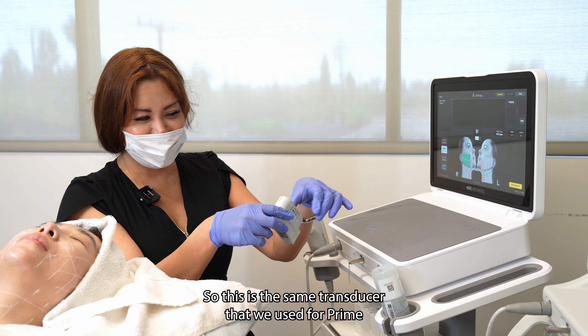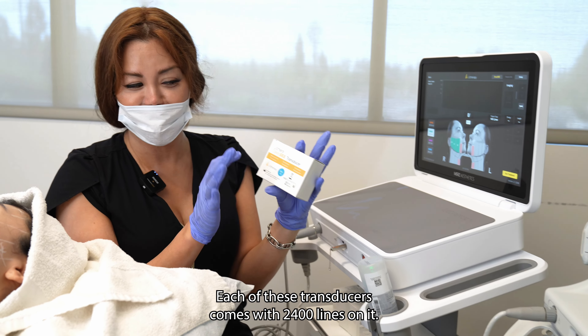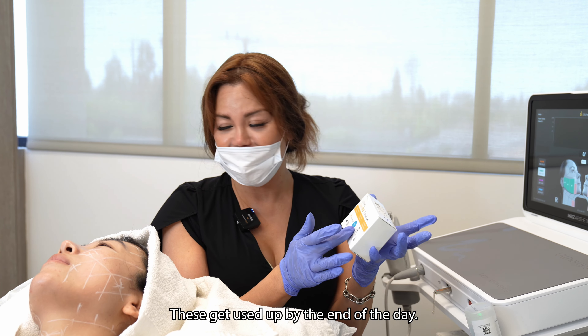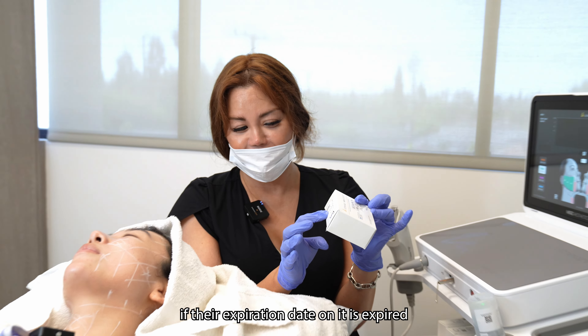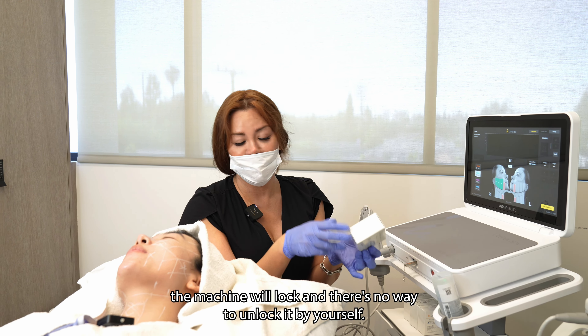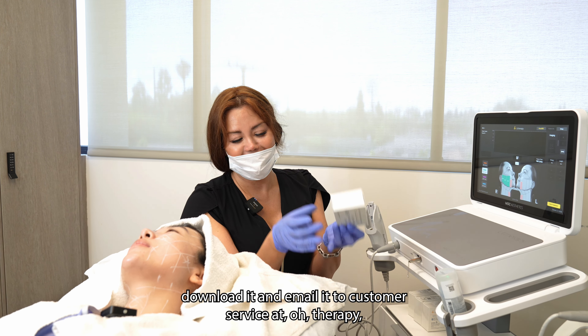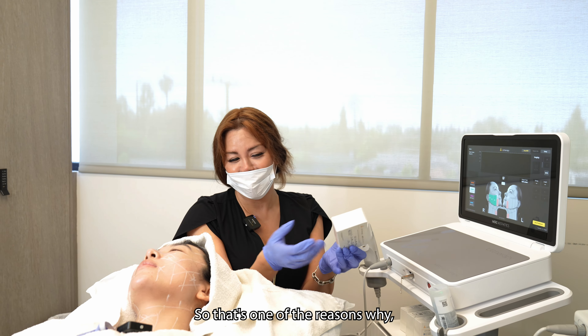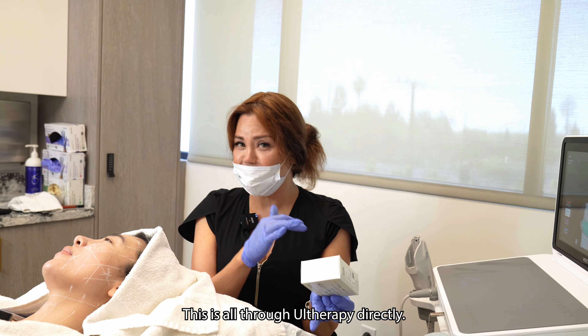This is the same transducer that we use for Prime that we're going to use for Ultherapy the original. Each of these transducers comes with 2,400 lines on it, and we, especially at WAVE, go through these extremely fast. These get used up by the end of the day. So all of these have an expiration date on them. If the expiration date is expired, or if there is some defect, the machine will lock and there's no way to unlock it by yourself. You have to download the record from the machine's computer and email it to customer service at Ultherapy, where they will analyze it and send you an unlock code. That's one of the reasons why we only stay with Ultherapy — we don't buy secondhand market machines. This is all through Ultherapy directly.